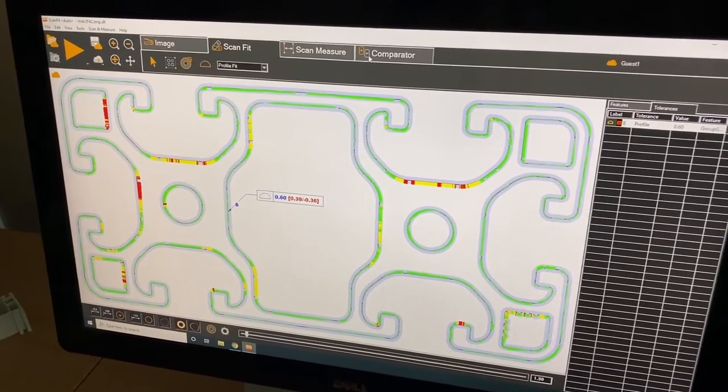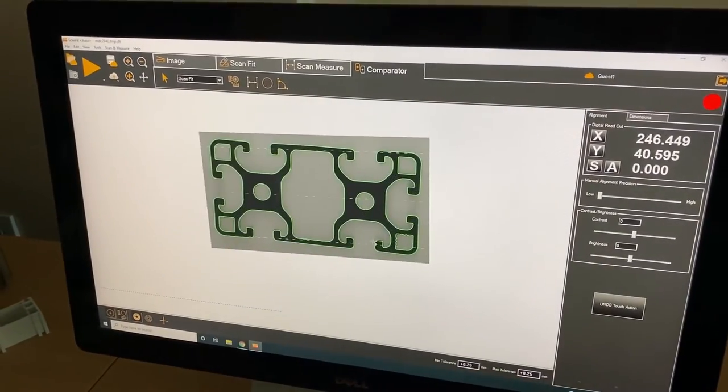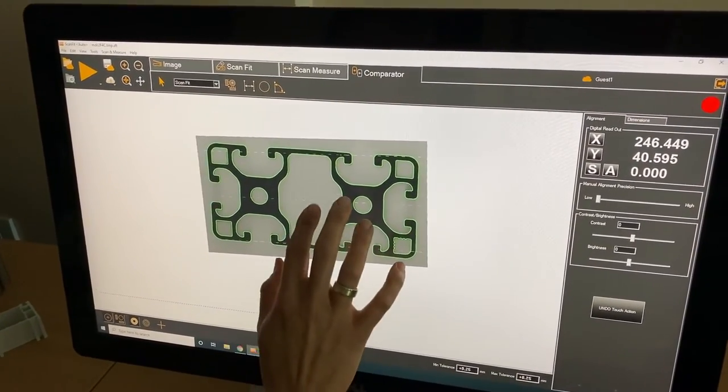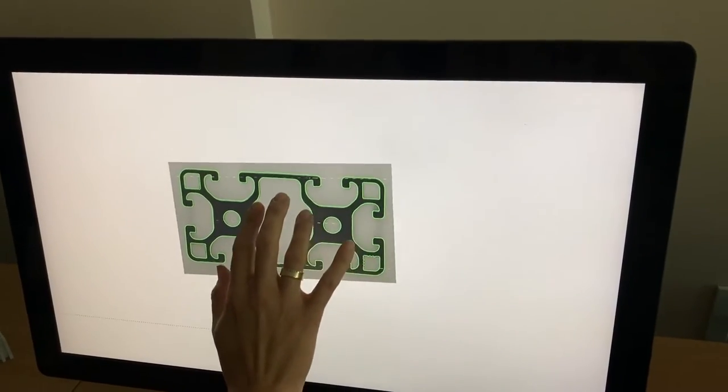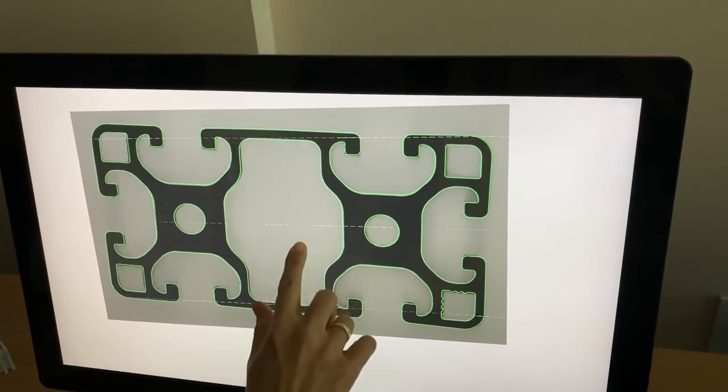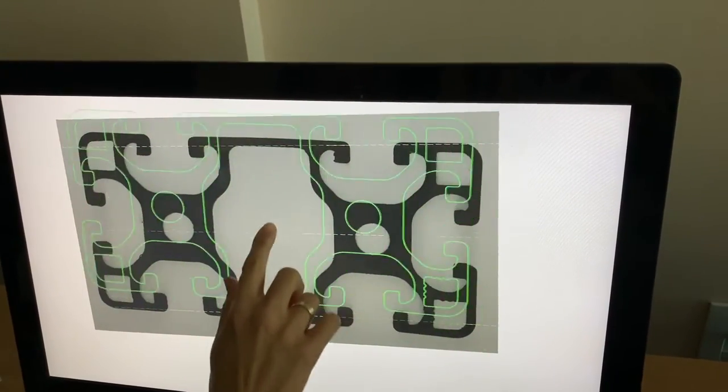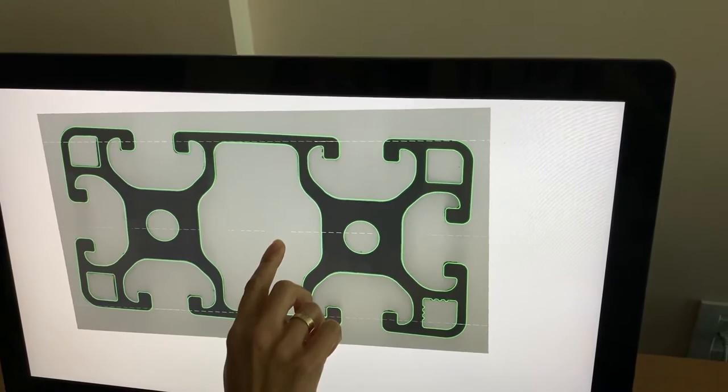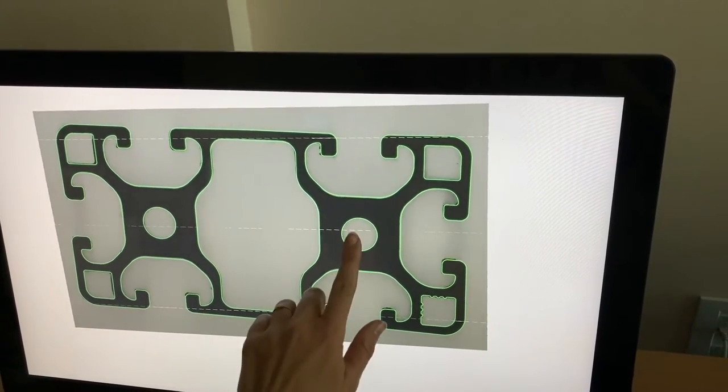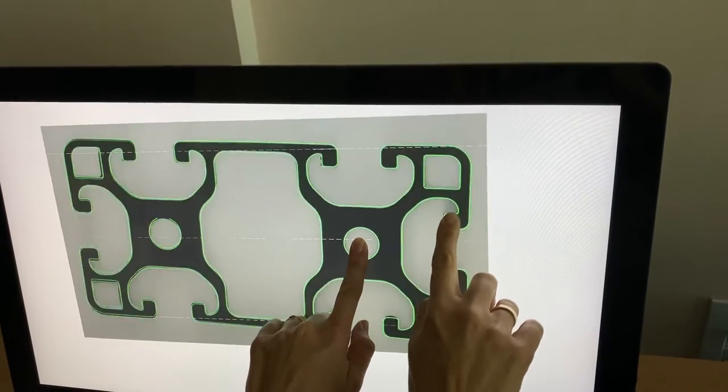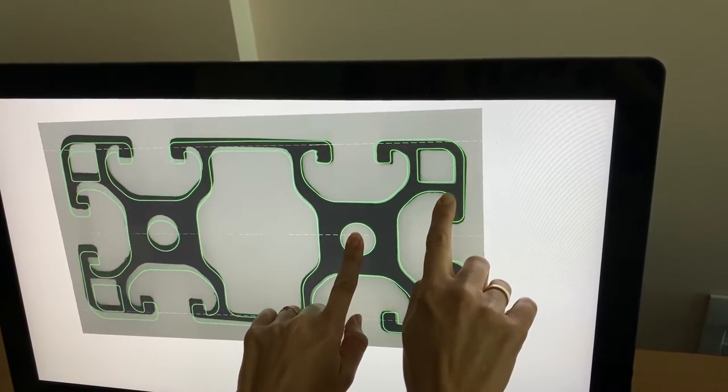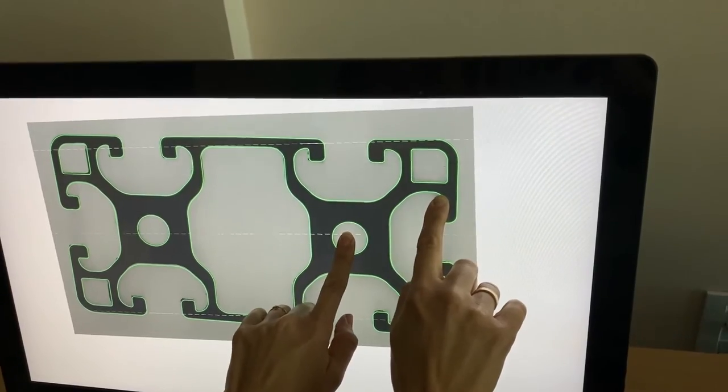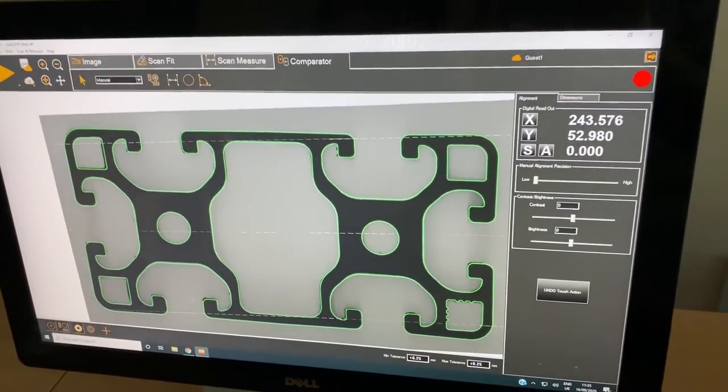The comparator tab simulates the work of a contour projector. We are using at the moment a touch screen monitor and you can see that we can manually adjust the nominal over the image. This is for operators that are used to working with contour projectors and would use this option of software.